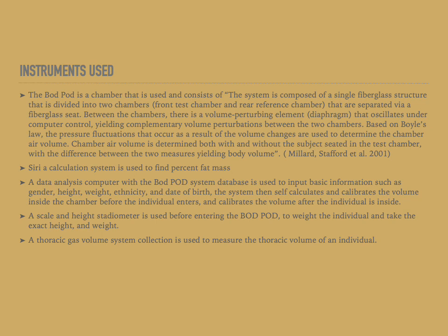The system self-calculates and calibrates the volume inside the chamber before the individual enters and calibrates the volume after the individual is inside. A scale and height stadiometer are used before entering the BOD POD to weigh the individual to the nearest kilogram and take the exact height to the nearest centimeter. An ADP machine is also used to measure the thoracic gas volume, which is the thoracic volume of an individual using the maximum tidal volume.